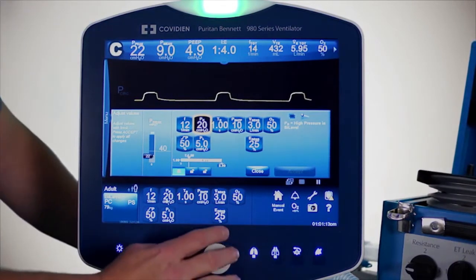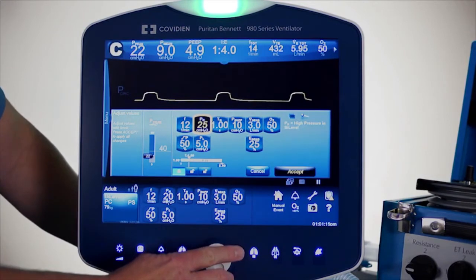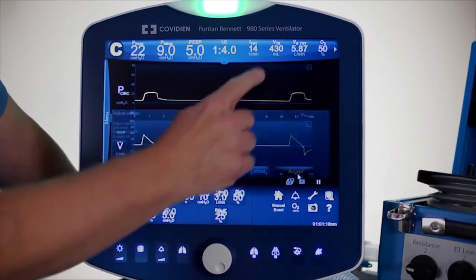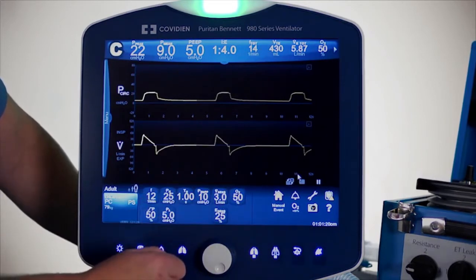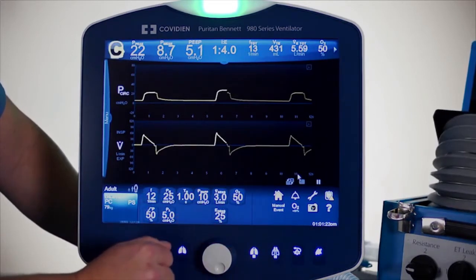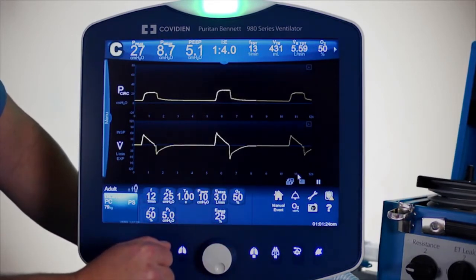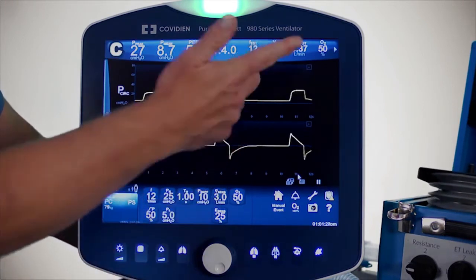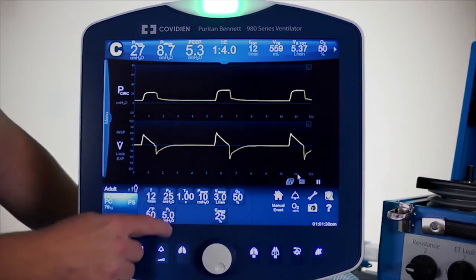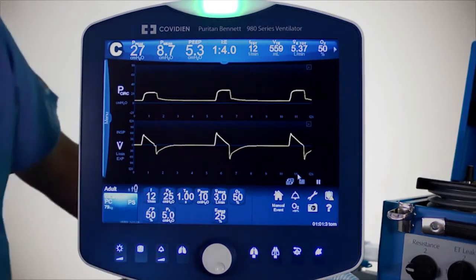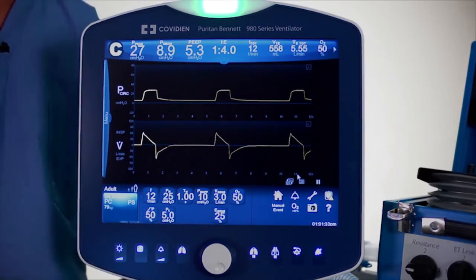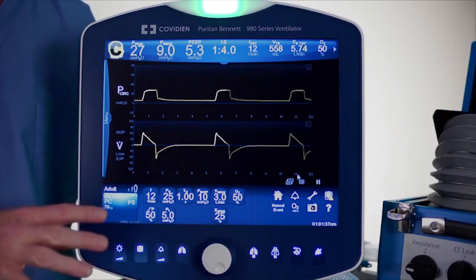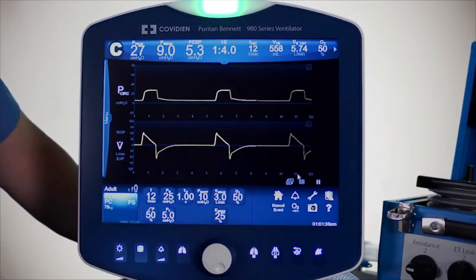In this scenario, I'm going to turn up the pressure a little bit to 25, just to demonstrate what happens to total volumes when you increase the difference between the pressures. After a couple of breaths, we can see the volume has gone up to 559 mL. It's that titration that determines what kind of total volume your patient will receive. This is what conventional ventilation looks like with some pressure support set.